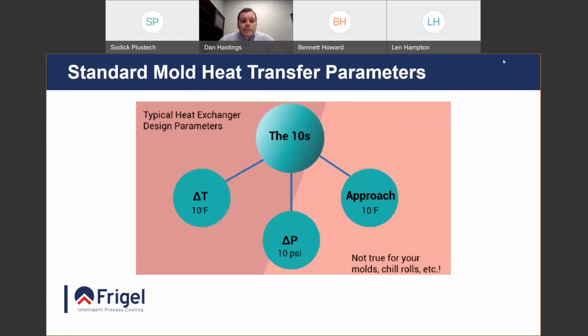Standard mold heat transfer parameters. This is something that at Frigel we try to let everybody know. The tens is something that a lot of people have been doing for many decades, maybe without even knowing it. What do you need for heat transfer for the mold? Well, let's have a small 3/4 horsepower TCU, and we have a 10-degree delta across the mold with a 10 psi pressure drop and a 10-degree approach between the cooling water system and the lowest temperature you can get on the temperature control unit. And this is really what I want to talk about, because does this hold true? Perhaps at one point it did, but we really should get away from this line of thinking.